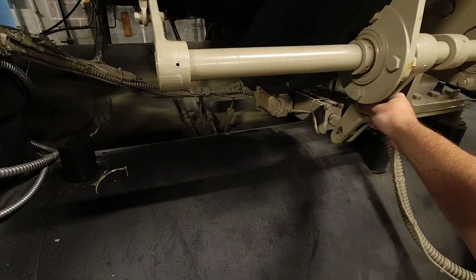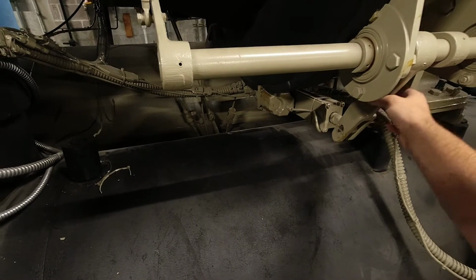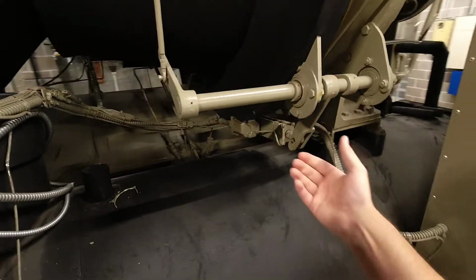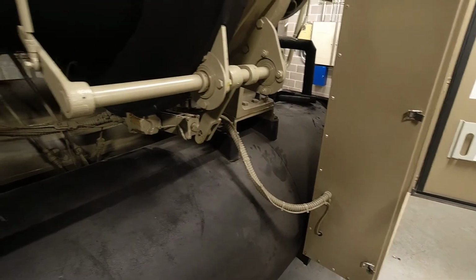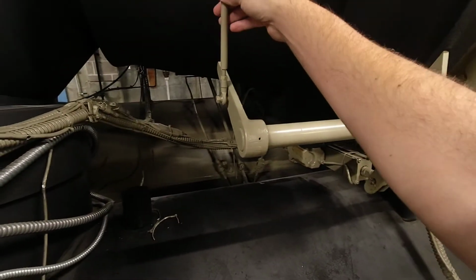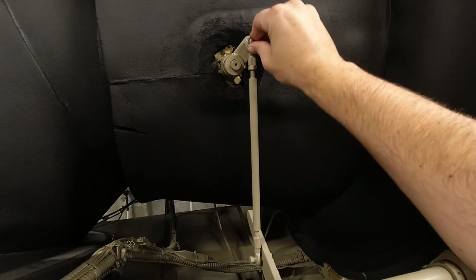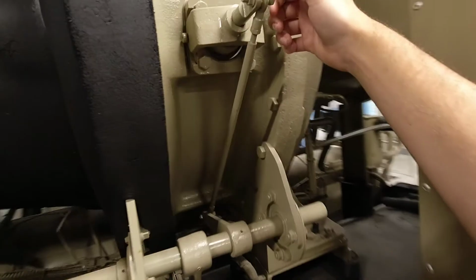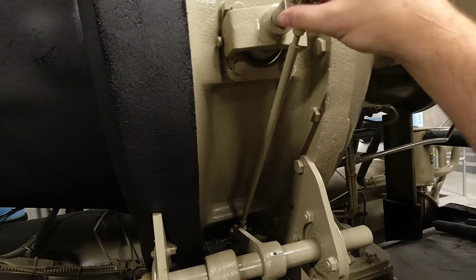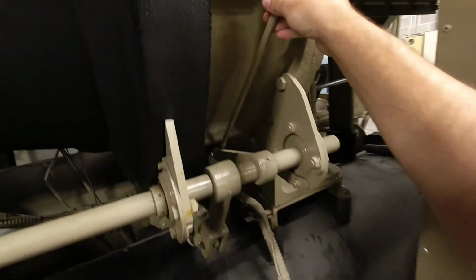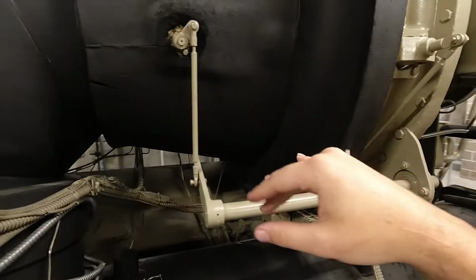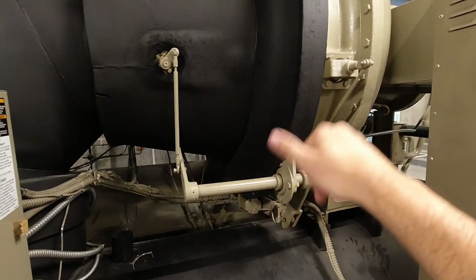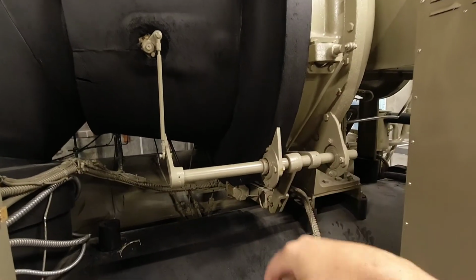This arm will routinely go through a calibration at startup, so that's one of the things you can expect as part of the process. You'll see it extend all the way out and come back in. You definitely want to make sure that all your joints and ligaments are properly tightened down and everything is moving freely. You do not want anything on these arms to bind. And these arms do swing together in unison.